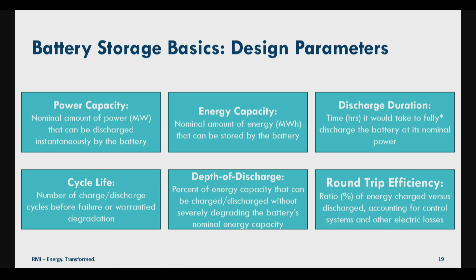Batteries are often not going to be discharged even to 80 or 90%. For example, for the frequency regulation applications I shared, these are very small changes in the battery's state of charge. If an operator did want to fully discharge the battery — and in some applications they might — in order to maximize the economic value of the battery, we want to make sure it can last as long as possible. That's why we wouldn't want to discharge it below that recommended depth of discharge. But if there's no need, there's no battery-life reason to hit that 80% mark, for example. That's right — the operation depends on the application, and there's no need to, for example, fully discharge the battery every time we use it.